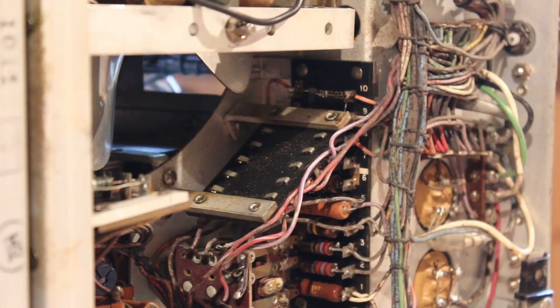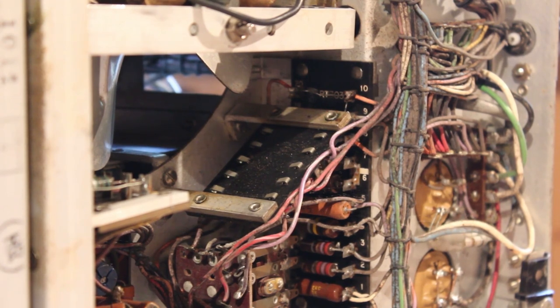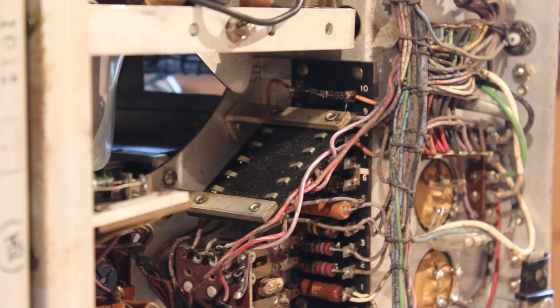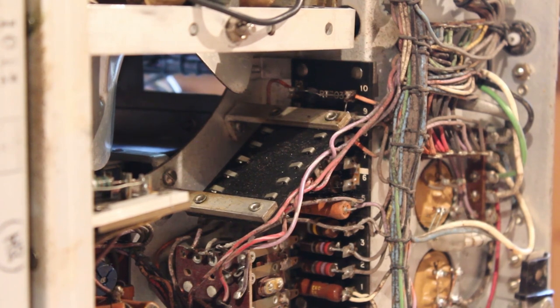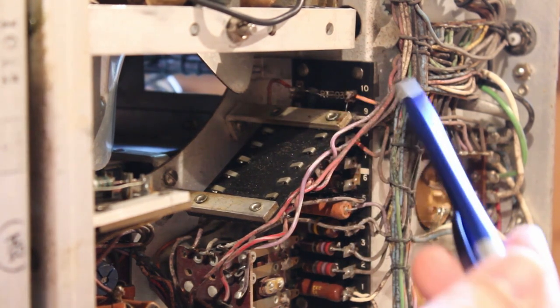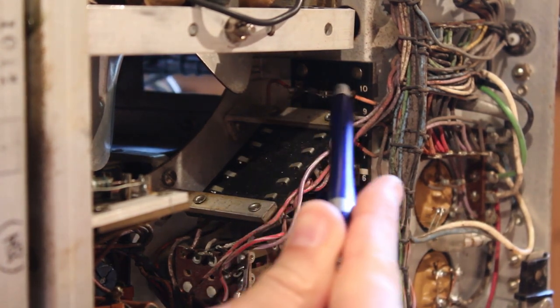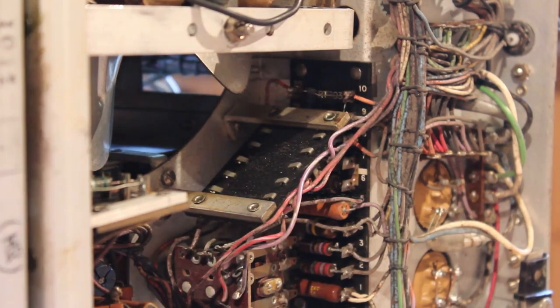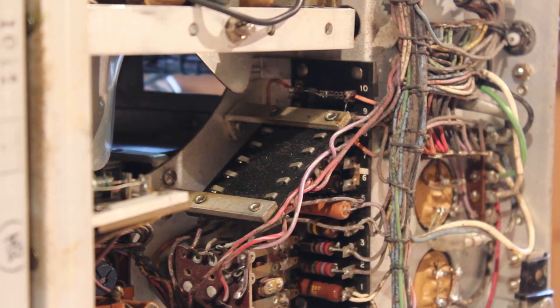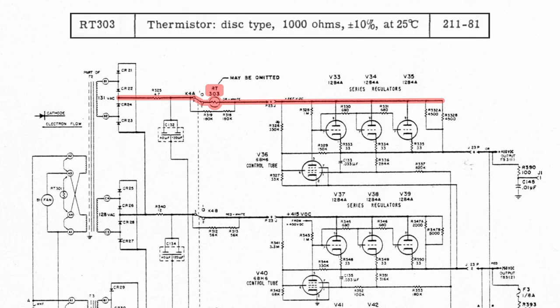And then to explain the last major issue, one of the times when I was testing it with the machine on its side, I noticed a spark when the time delay relay kicked off. And at first I thought this was just the contact sparking. But when I double checked it, I noticed that it wasn't coming from the relay itself. It was actually coming from above at this little component right here called RT303. If we look at the schematic for the low voltage power supply, RT303 is a 1000 ohm thermistor that is on the very high voltage rail. So there's a lot of juice going through it. But I think our thermistor here is good and dead. So that's going to need to be addressed.